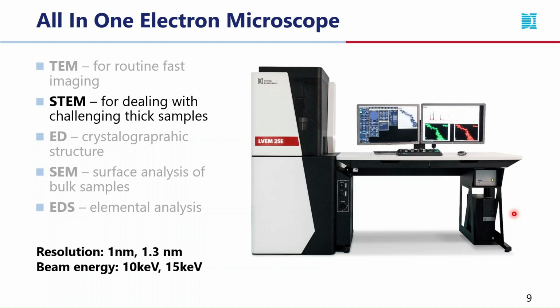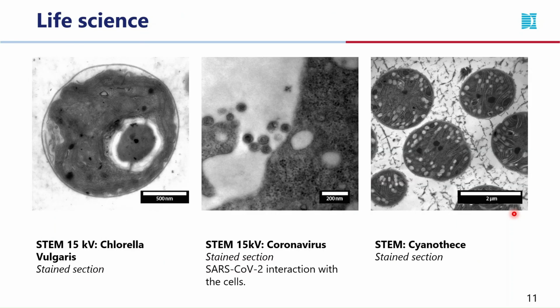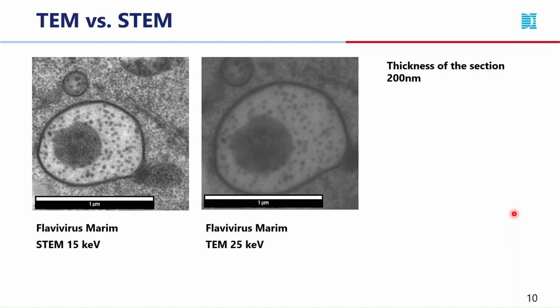STEM imaging properties will especially be appreciated by customers from life science who want to work with thicker sections, because scanning transmission is not sensitive to the additional broadening of energy spectra by the sample itself, and thus it deals better with chromatic aberration. Here is an example of very thick sections of about 200 nanometers, which can serve as proof of STEM capability to handle blurred TEM images caused by the interaction of the electron beam with the sample.